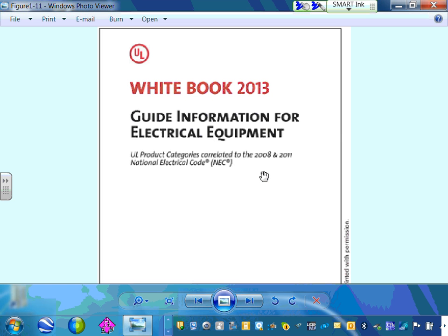Say someone grabbed a lighting fixture from a hometown in the Middle East and brought it to install in Minnesota, and you're the project manager. You ask, is this listed? They say yes. Where is it listed? UL. Do you take their word for it? What's your listing number? They give you a number—but where would you verify if this number is right or wrong? The white book. You go there—it's a book for project managers—and verify that what they're telling you is correct, because you can't just take anyone's word for it.